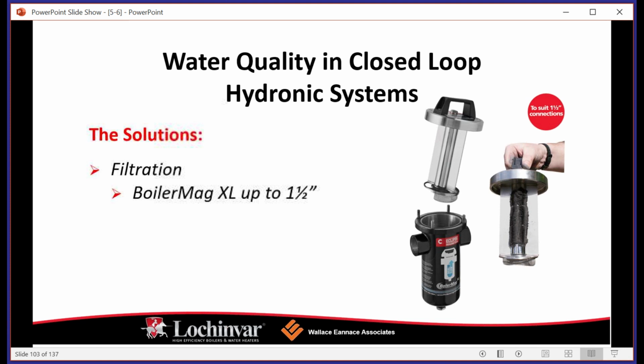So again, low flow. Not your father's boiler. We kind of discussed that before too with water tube boilers. It's a narrower passage, whereas on an old heat exchanger, it was like a tea kettle, right? You can fill that thing full of freaking Skittles. It's not going to really care. It's just going to run and boil the water and send it on its way. When we're talking about efficiency, particularly with water tube equipment, if those water tubes are getting full of lime and scale, it's going to clog, it's going to be inefficient, you're going to have failures, and you're going to basically lose all the advantages that we had from that condensing technology due to bad water.